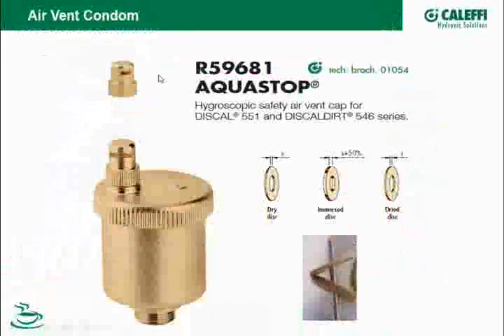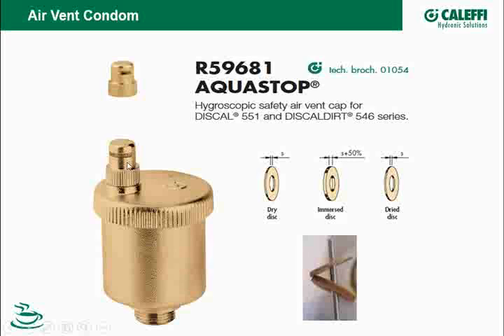Another cap along the same lines is called an AquaStop cap. You can buy this as a separate component. Some of our air vents come with this already installed, and basically what it is, it's got a cap with a bunch of these cellulose fiber discs in it. So as soon as these discs get wet, like this one I've got here on a paper clip that I dipped into a cup of water, they swell up, and so you get a second level of protection. So in addition to having the float and the little needle valve that shuts off right underneath here, this gets you a second level of protection.